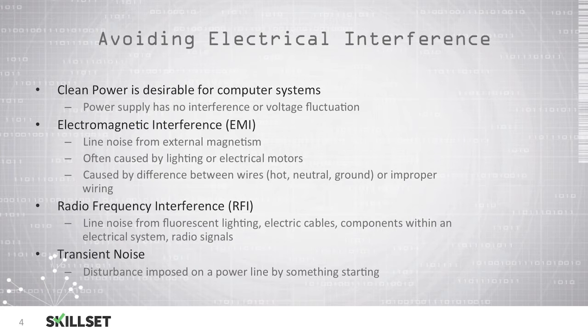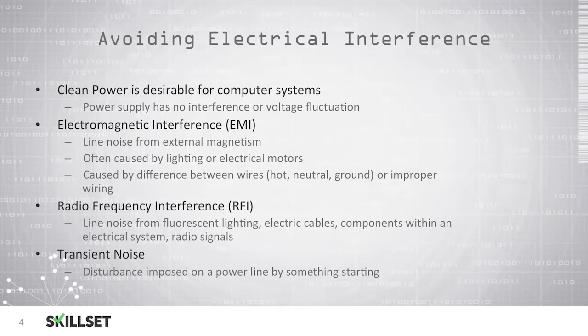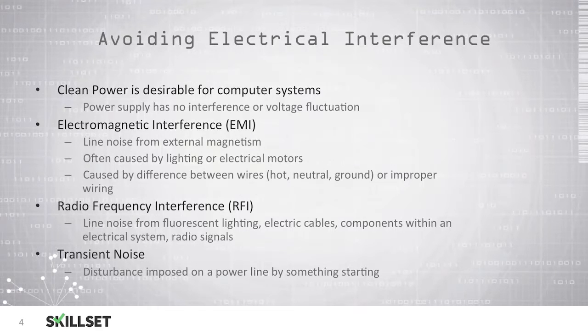It is important to make sure that you avoid electrical interference and have clean power for your computer systems. You want to make sure that there is no interference or voltage fluctuation because this can damage your equipment. Electromagnetic interference or EMI is line noise caused from external magnetism, which can be caused by lighting or electrical motors, or by improper wiring differences between the hot, neutral, and ground wires. Radio frequency interference is line noise from fluorescent lighting, components within an electrical system, electrical cables, or even radio signals. Transient noise is a disturbance imposed on a power line by something starting, such as a large motor or a piece of heavy equipment. You should attempt to avoid these types of interference as much as possible in your environment.